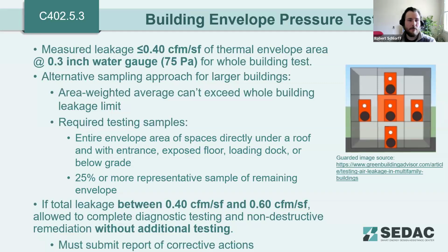So in this case, you're going to be required to test samples that are the entire envelope area of spaces directly under a roof, spaces that have an entrance, spaces that have an exposed floor, a loading dock, or spaces that are below grade. So all of those spaces need to be tested, and then 25% or more of a representative sample of the remainder of the building after you account for all of those spaces listed in the first bullet point there.